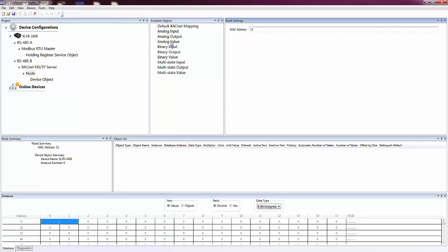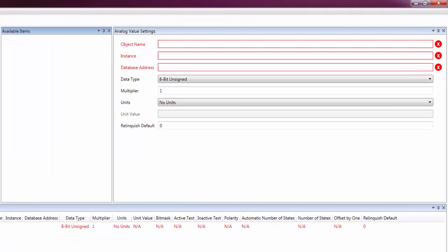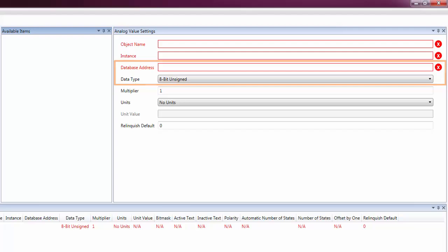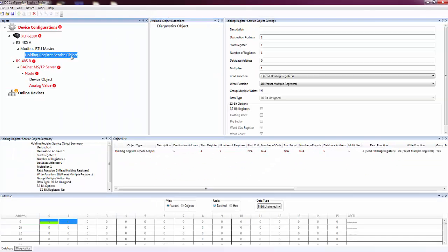Finally, we need to map a BACnet object to the Modbus holding register we created earlier to expose that data on the BACnet network. The two settings to make note of here are the database address and data type. These settings must match the settings we used in the Modbus service object.